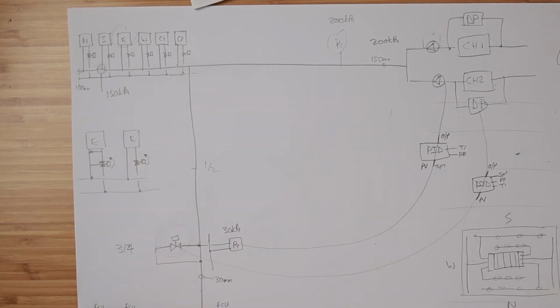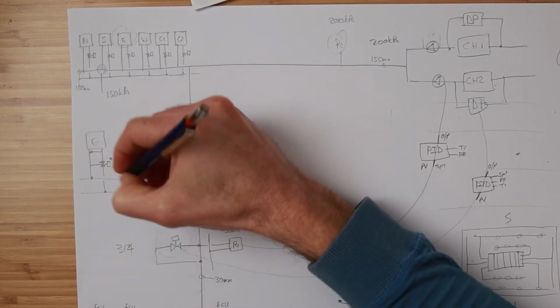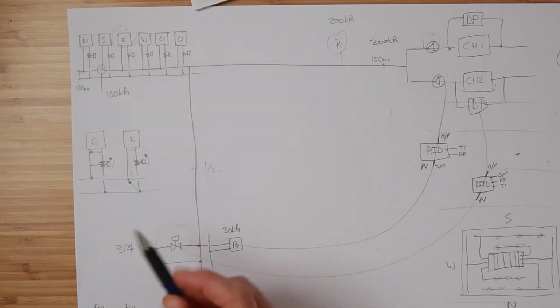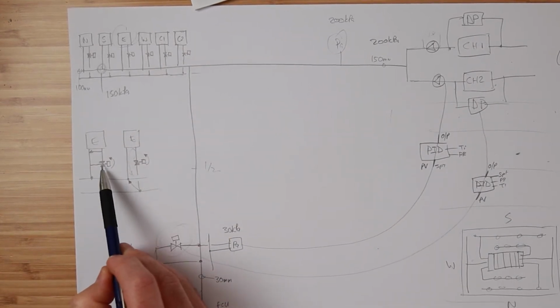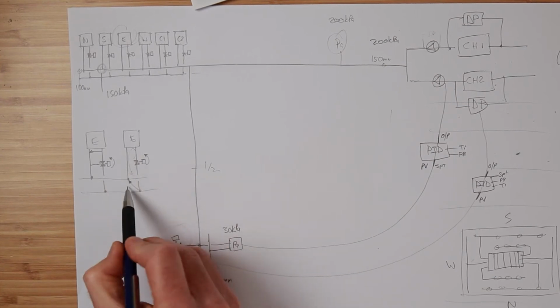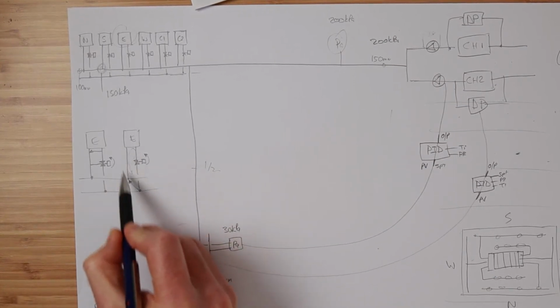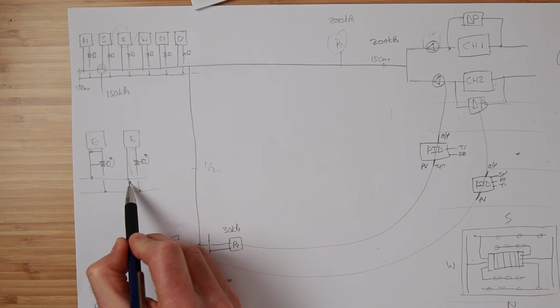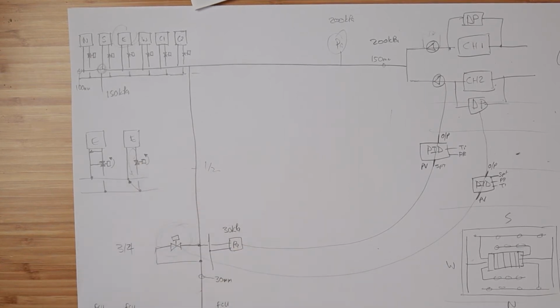For a two-port system, the valve authority is the pressure drop across the valve, and the way it's described in books and on the internet is it's the rest of the circuit pressure, which I think is this pressure here, but I might be wrong. Probably not. So you can see that with a three-port system, the point I'm making here is the system pressure of the local branch there is what determines the valve authority and good control over the system.